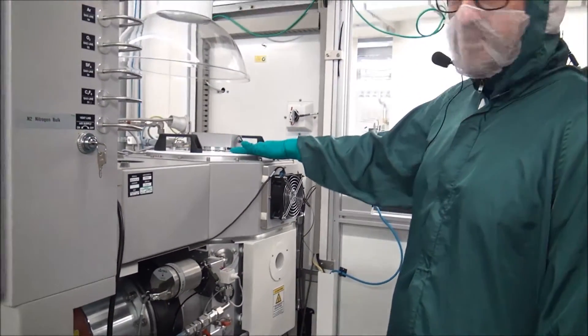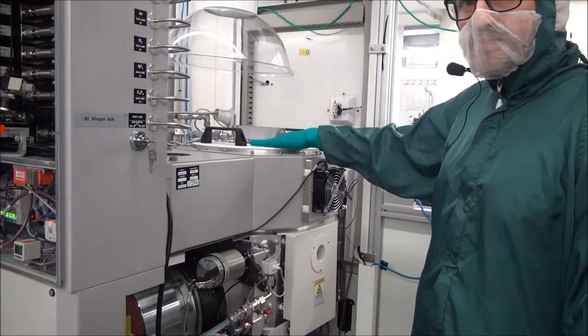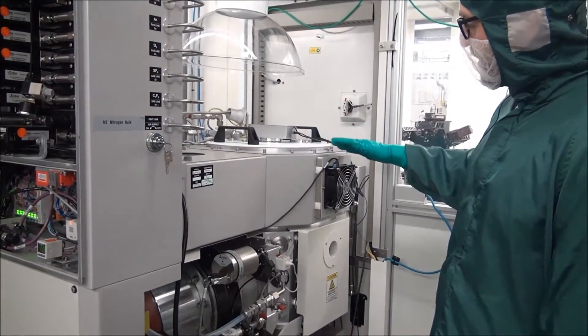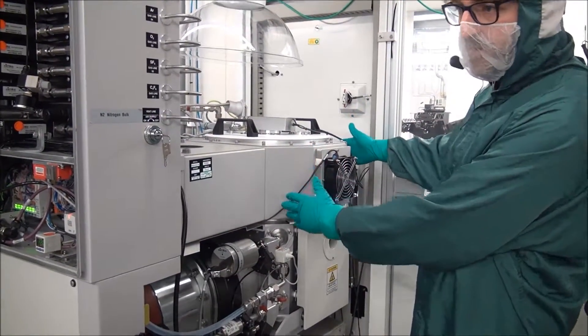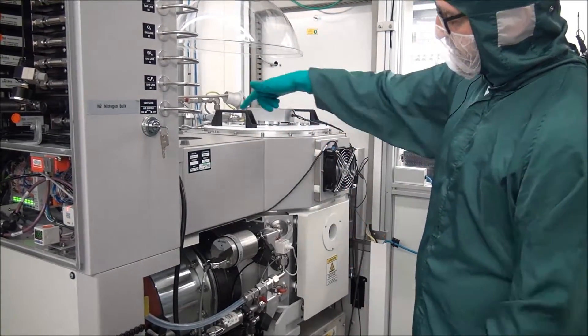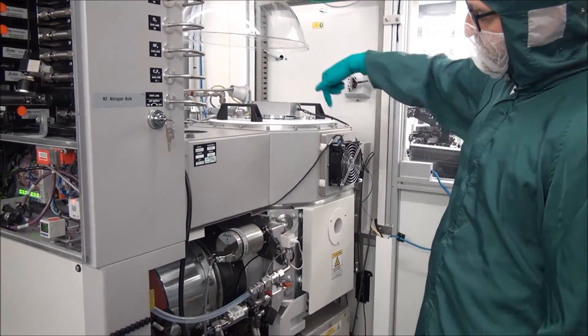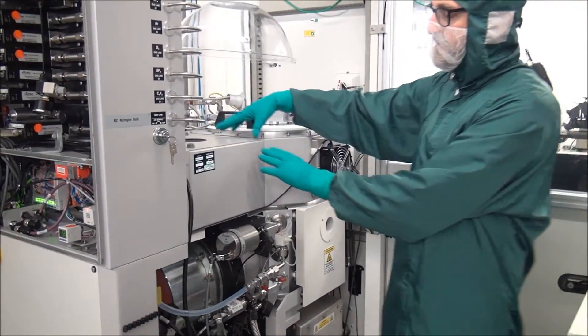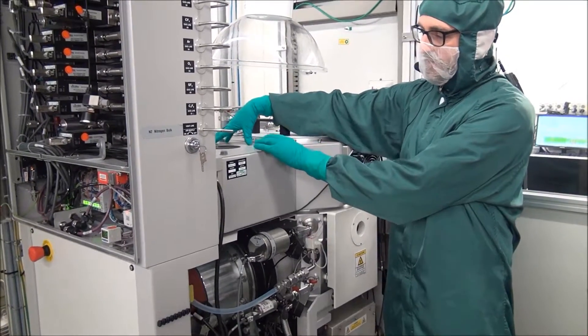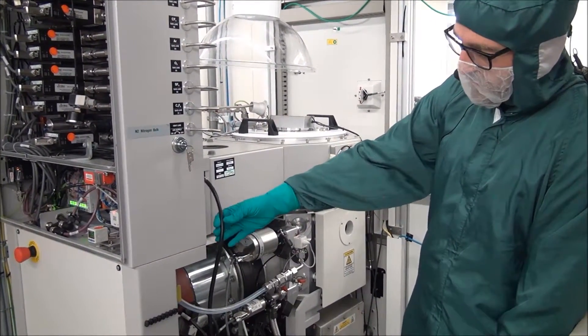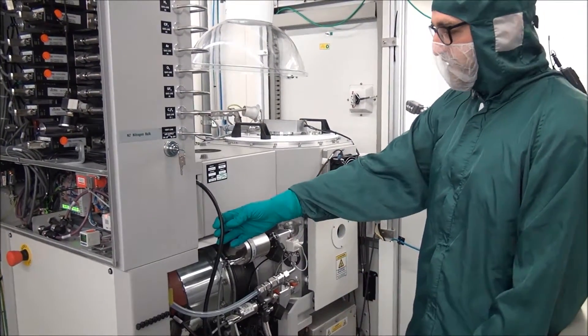Here we've got the top lid. This is heated normally to 50 degrees. We have the main body of the chamber which is basically a big piece of ceramic with an electrode that goes around it. Connected to the electrode we have a matching unit which is located inside this box here, and of course an RF cable which is going to the RF generator.